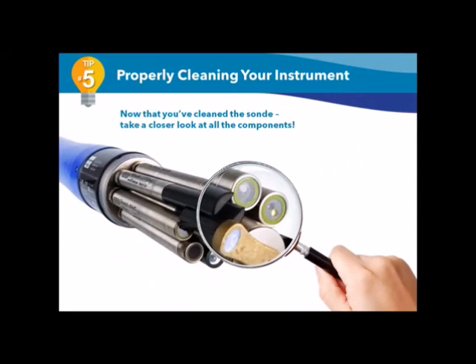So then after all of your cleaning has been performed, you should carefully look over your instrumentation. You should check the cable's integrity and connectors and ensure that the connectors are free of debris. I like to apply the grease with my bare fingers to areas like O-rings and connectors, because this lets me catch nicks or grit that could compromise the seals.